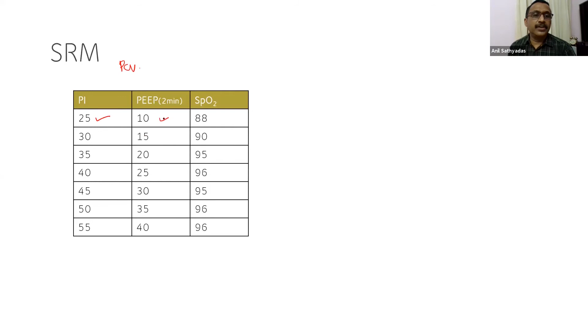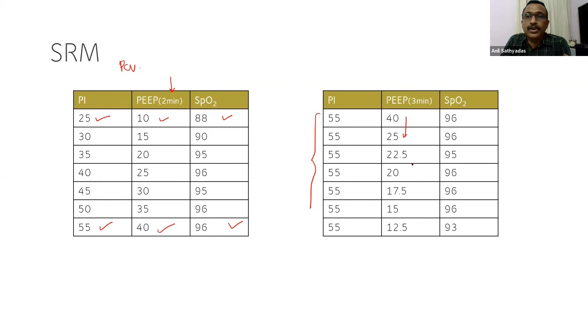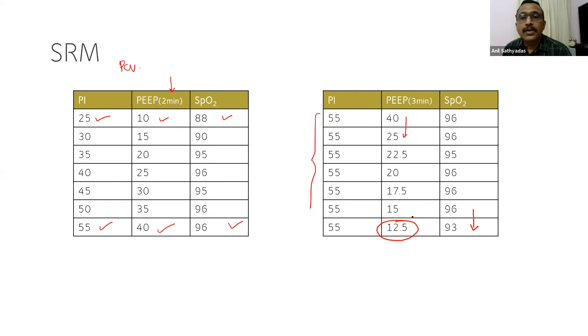That is because more alveoli have opened up. The second step you have to do here is to maintain that PI at 55, and come down on the PEEP. First step is to drop directly to 25, and then from there 2.5 decrements every 3 minutes and monitor the saturation. What would happen when you decrease the PEEP? There would be a point in time when many of the alveoli would collapse because of the low PEEP. They don't remain open. PEEP keeps them open. It recruits alveoli. So you can see the drop in saturation. This is the de-recruitment point.